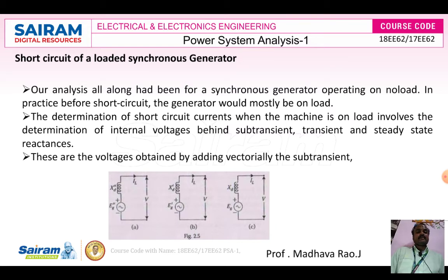But when the system is on load, all the phase currents are not the same, so the system is under unbalanced condition. We cannot use the single phase technique to analyze the short circuit current. So the determination of short circuit current when the machine is on load involves the determination of internal voltages behind subtransient, transient and steady state reactances.